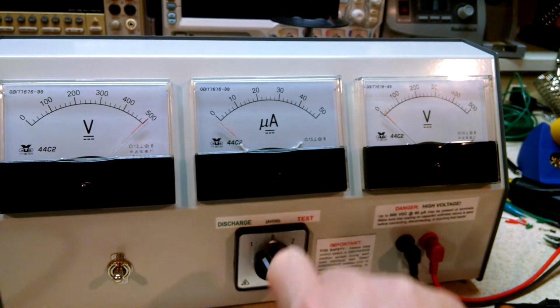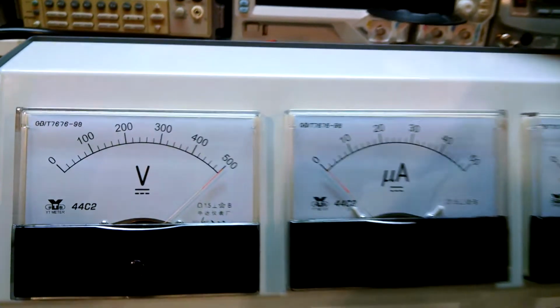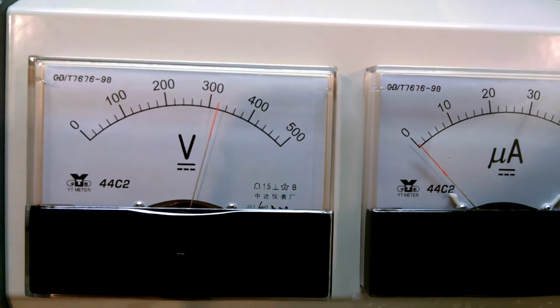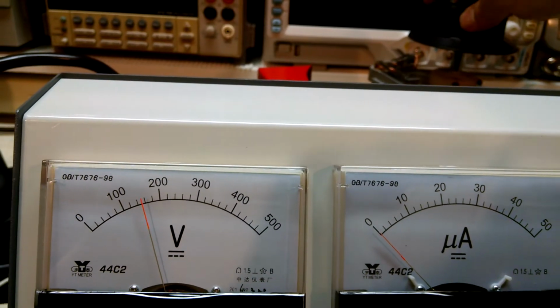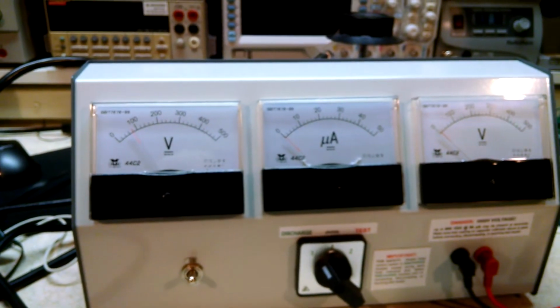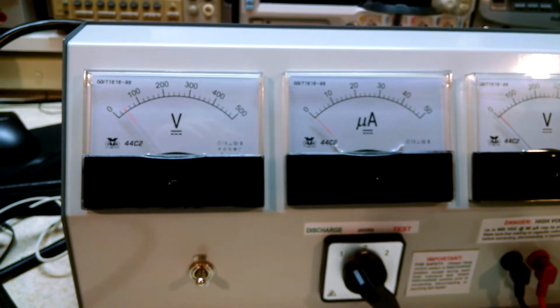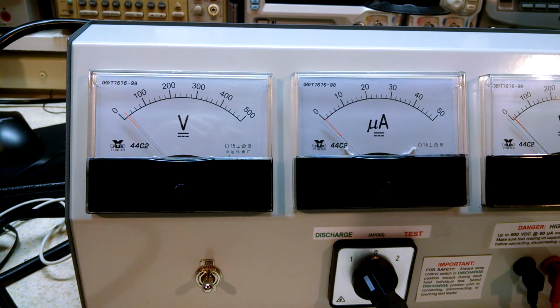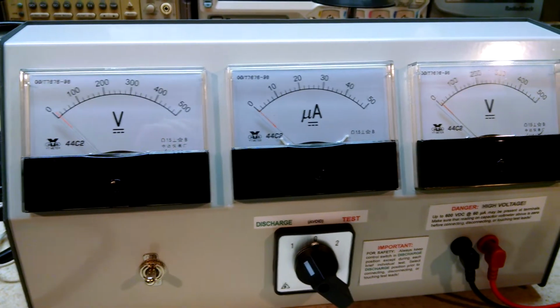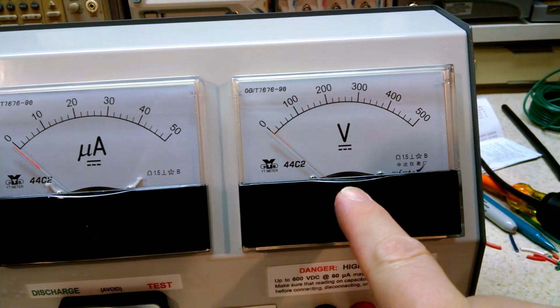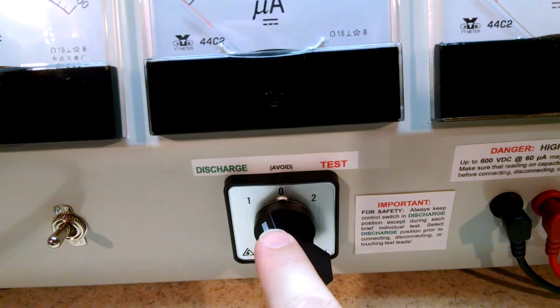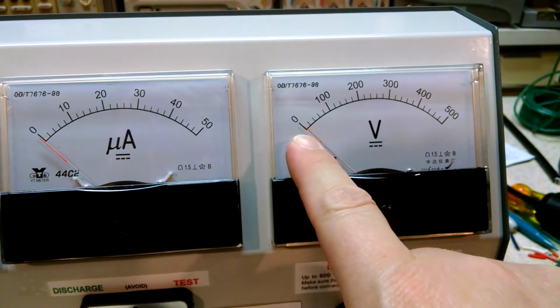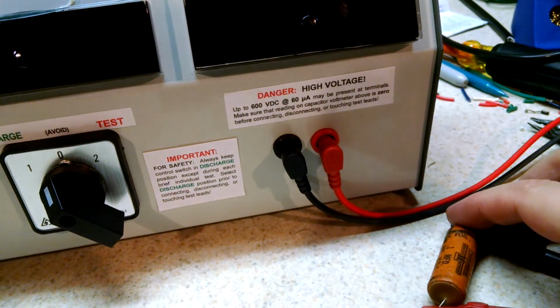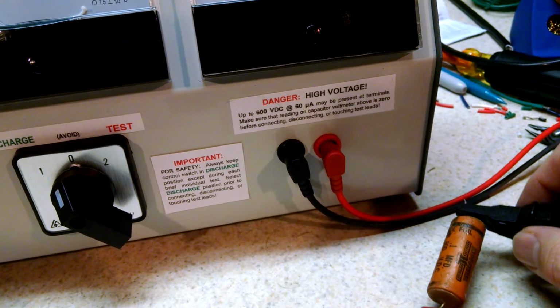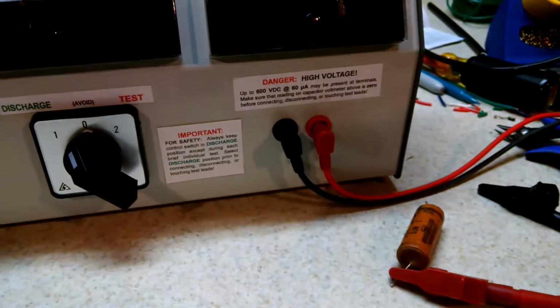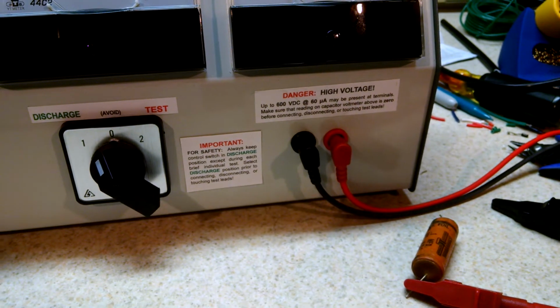Alrighty, we'll go back to discharge. And we'll wind down the voltage here. And the internal power supply capacitors are discharging down to zero. And as we can see over here, this is the voltage on the capacitor. Since we're in the discharge position, this tells us the voltage across the capacitor, so now I know that this is safe. I can touch this, no problem. Alright, we're going to put it on pause here for a moment, come back with a good capacitor.